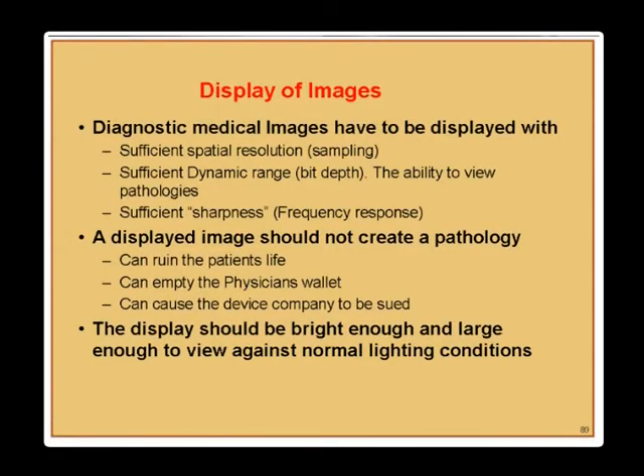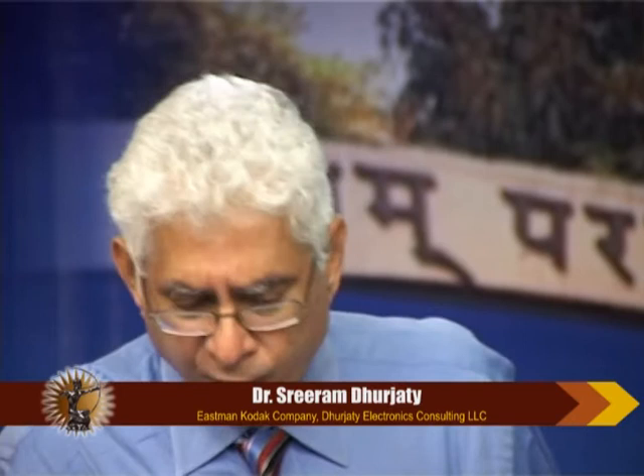The display should be bright and large enough for normal radiologist-suite lighting conditions — not fully dark, which causes eye fatigue. Viewing angle is also important: at 45 degrees, many displays look poor. New organic LED displays — a Kodak invention — are isotropic with angle, allowing multiple viewers to see the same image simultaneously.